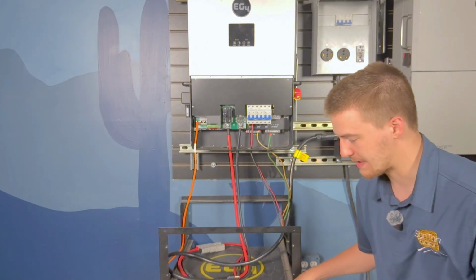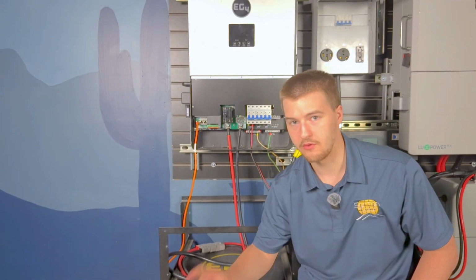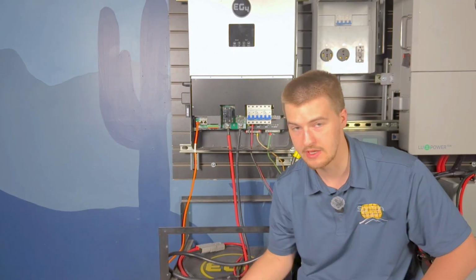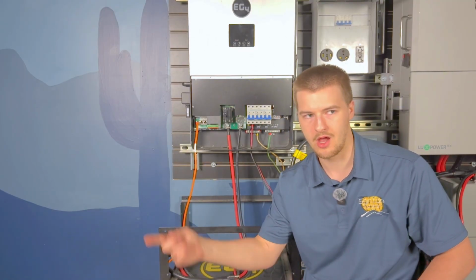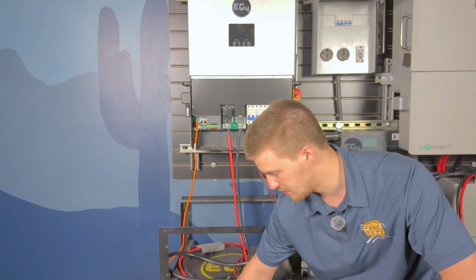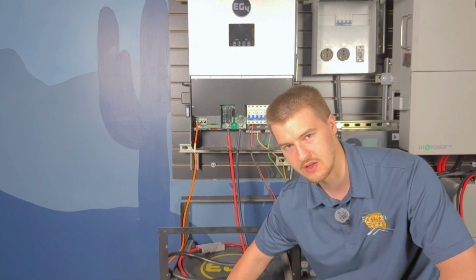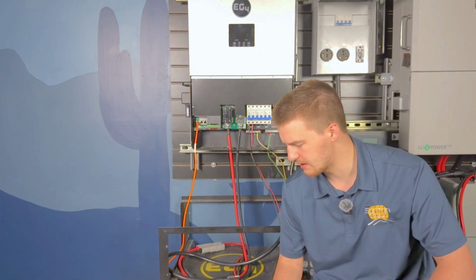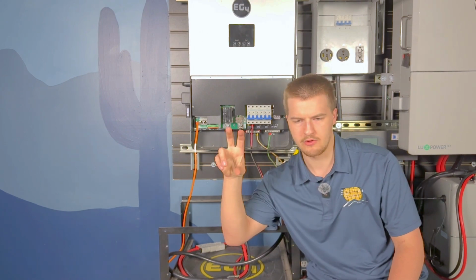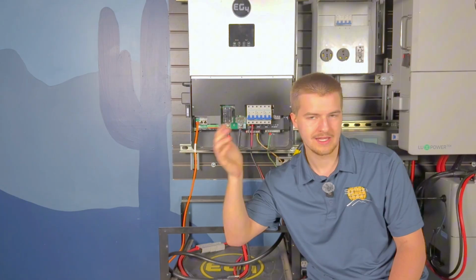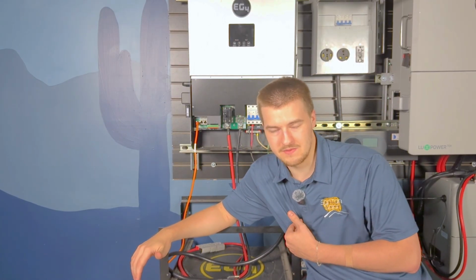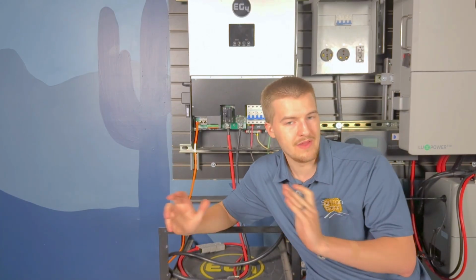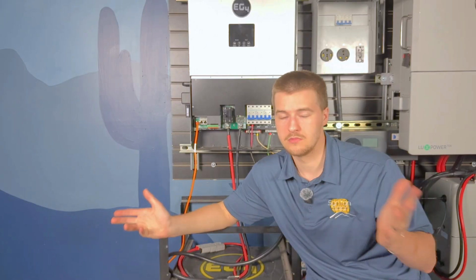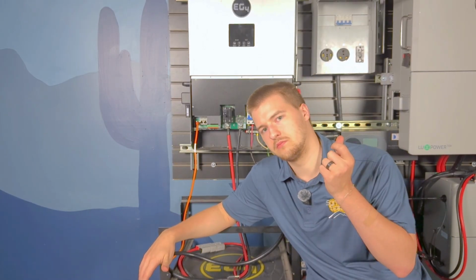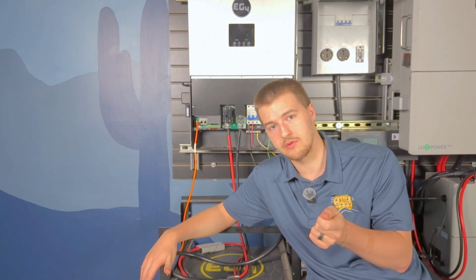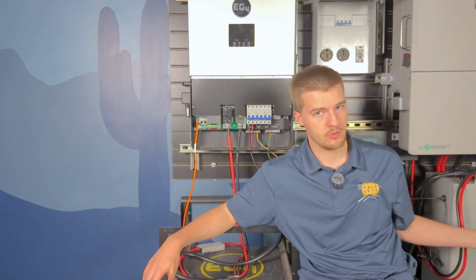Then we have our battery connections. If we're paralleling, we're going to go from BAT COM, and you'll see that with your green cable that you get with your batteries. You'll go BAT COM - I've seen it go COM BAT, your COM port. I'll put an image on screen so you can see what I'm looking at. I've seen it go COM port to your battery ports, and I think that's fine - again, check the documentation. I've always done it and always been taught to do battery port to COM port. If that's different or changed depending on firmware, then it's changed depending on firmware, right? But as of right now, battery port to COM port with your green cable that you get with your batteries, whether it be rack mount or wall mount. Cool?